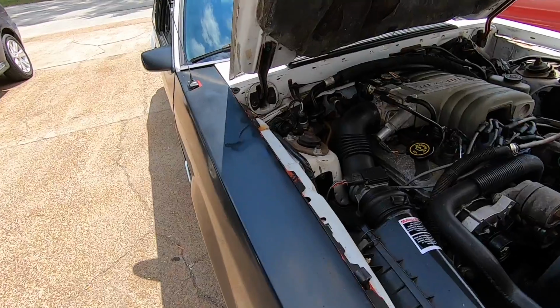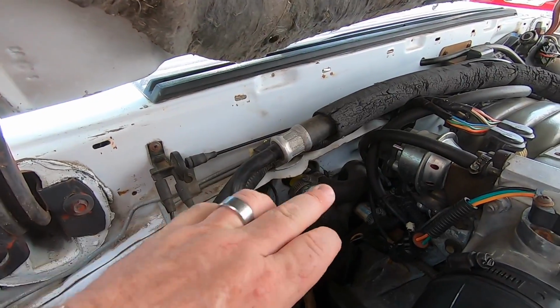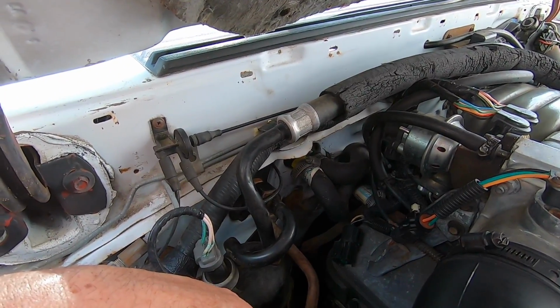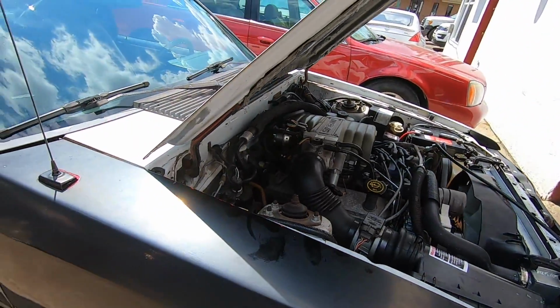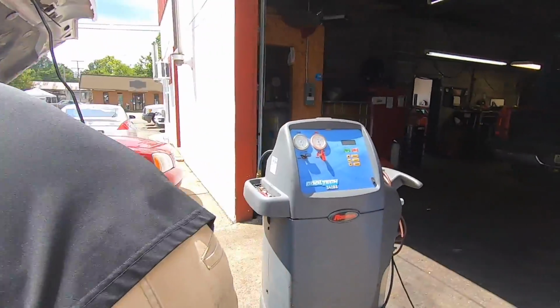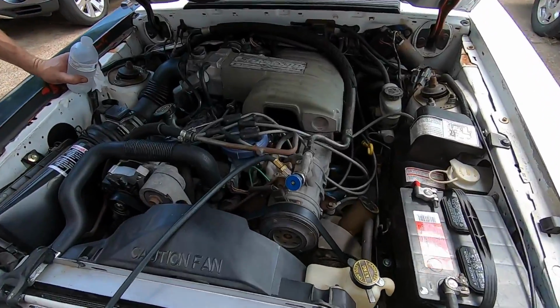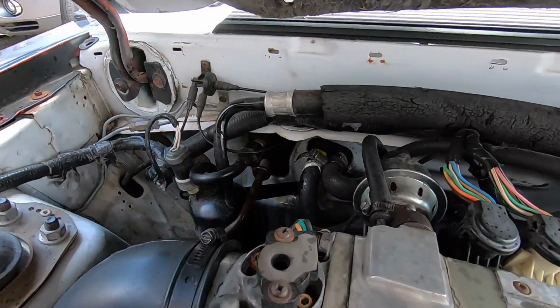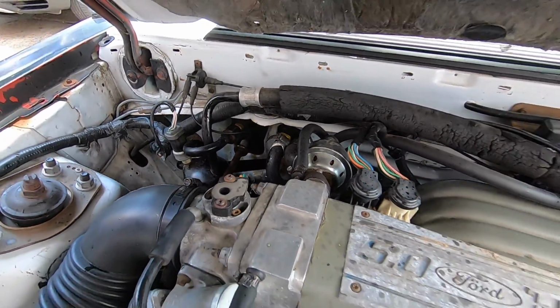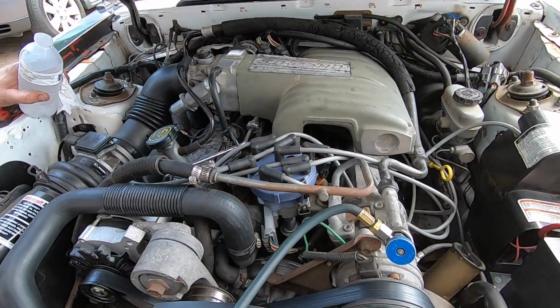That'd be a start. Okay, guys, so we're not dead yet. We found this. The dryer wasn't even hooked up, and so that's possibly why it wasn't pulling vacuum. We're fixing to tighten it up and try to pull a vacuum again. See what it does. All right, guys, this takes 2.5. Yeah, that bottom line was disconnected too. Man, that stuff is terrible. It stinks, but we're filling now.